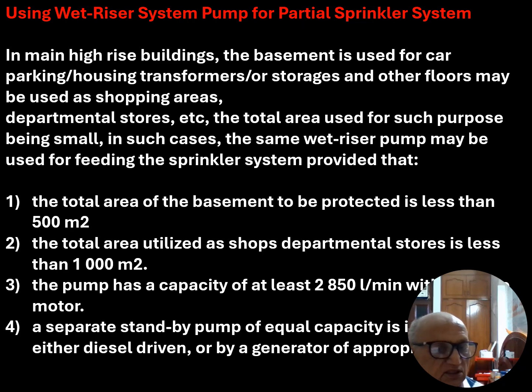for feeding the sprinkler system, provided that the total area of the basement to be protected is less than 500 square meter. The total area utilized as shops and departmental stores is less than 1000 square meter. The pump has a capacity of 2850 liters per minute with an electric motor. A separate standby pump of equal capacity is provided, which may be either diesel driven or driven by a generator of appropriate size.